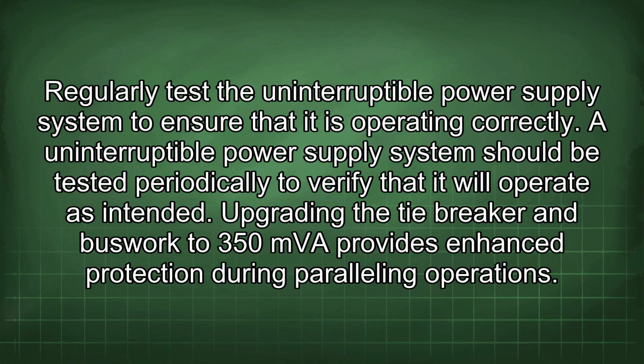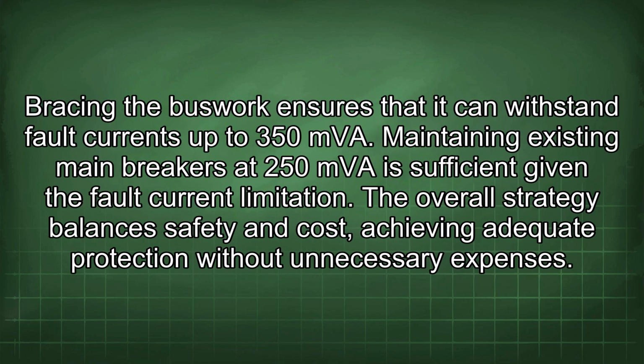Upgrading the tie breaker and buswork to 350 MVA provides enhanced protection during paralleling operations. Bracing the buswork ensures that it can withstand fault currents up to 350 MVA. Maintaining existing main breakers at 250 MVA is sufficient given the fault current limitation. The overall strategy balances safety and cost, achieving adequate protection without unnecessary expenses.